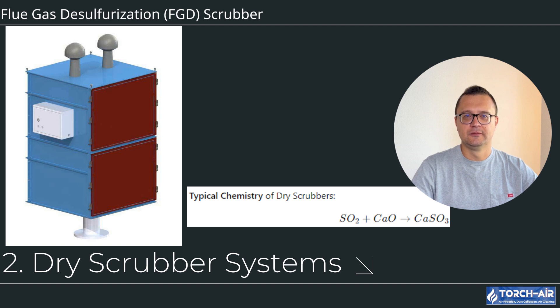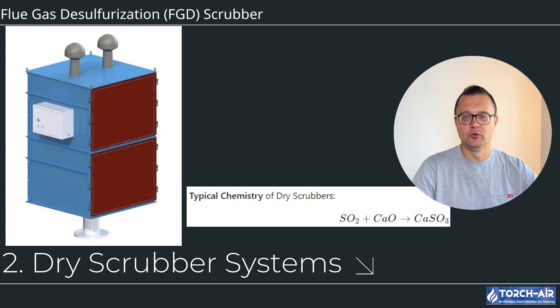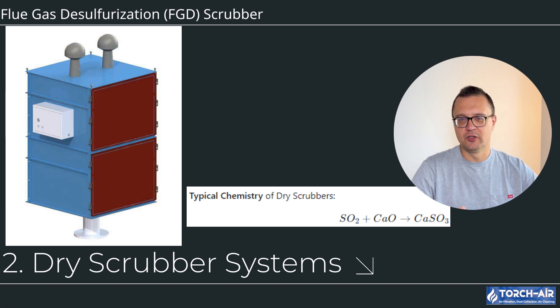Dry Scrubber Systems: Dry scrubbers are used where water consumption is a concern, or space constraints make wet scrubbers impractical. Like wet systems, the flue gas enters the dry scrubber through a gas inlet. A powdered sorbent, typically lime (CaO) or sodium bicarbonate (NaHCO3), is injected into the gas stream. The dry sorbent reacts with SO2 to form a solid byproduct, such as calcium sulfite.